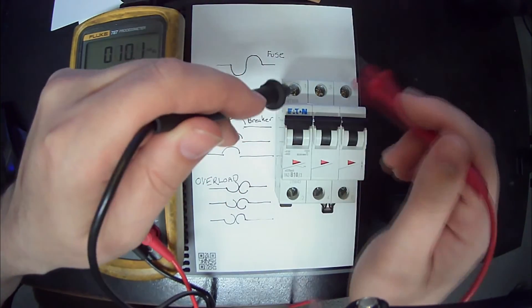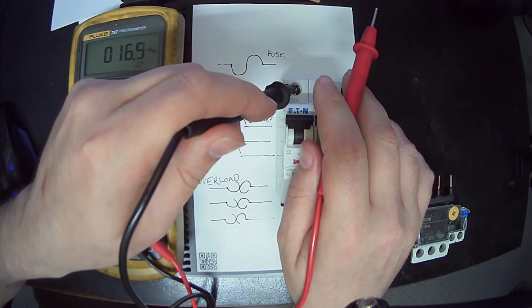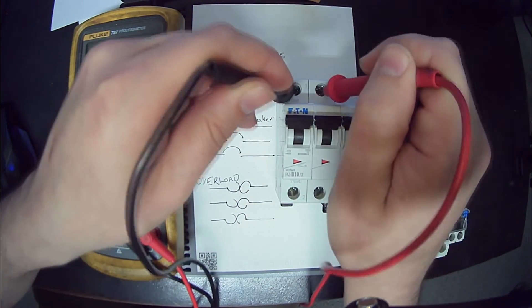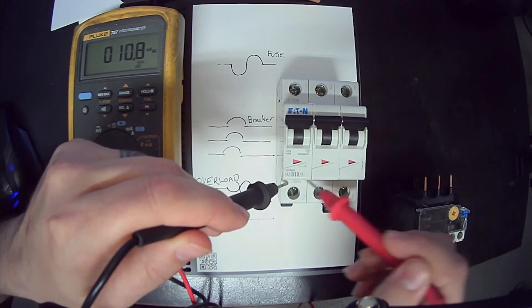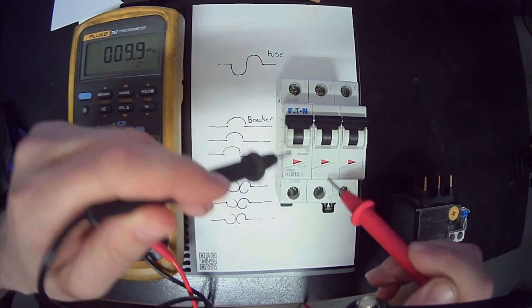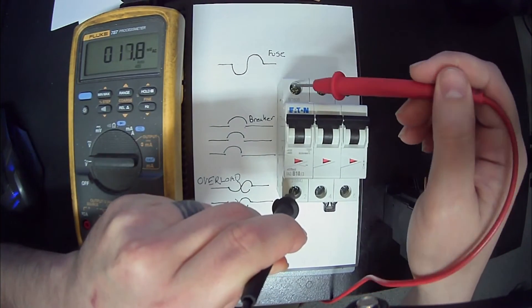Matter of fact, today I came across there was two blown fuses on a shredder feeding a reclaim system. So I imagine some of you guys know what that is out there. Knowing that it's just leg to leg here, but I'm wanting to test my breaker. So I'm wanting to test this side of it.